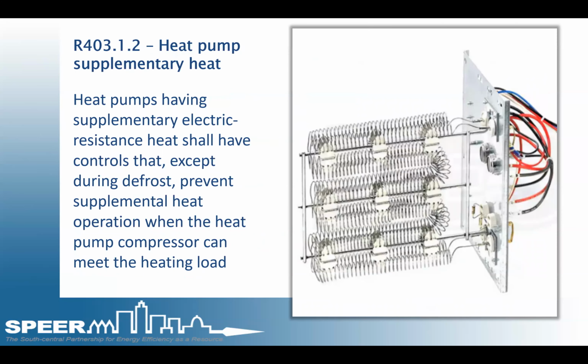So 403.1.2, heat pump supplementary heat, also called emergency heat or supplemental heat. Heat pumps are great pieces of machinery because they move heat instead of creating heat. There are no byproduct losses, which means these are highly energy efficient compared to gas furnaces. Their only downfall is during their defrost cycle or when the outside temperature is too cold. In most cases, the electrical resistance heat will have to come on and waste huge amounts of energy if the compressor alone cannot meet the load when running in heat mode.